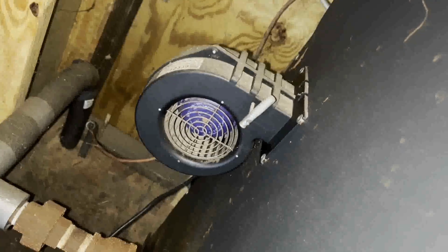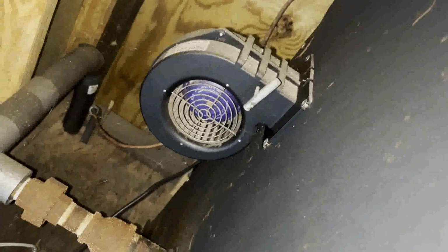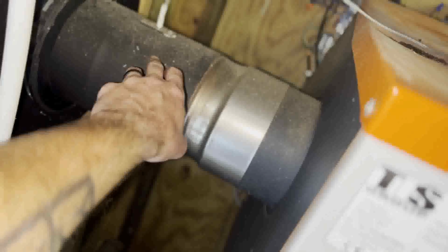I will show you back here. There's the blower. It's a variable speed blower. It's got a barometric damper in it, so as the speed speeds up or slows down, that will open. Flue gas data is collected right there. But yeah, it's completely variable speed, and it works great. So I'm going to show you some of the other stuff in the system.